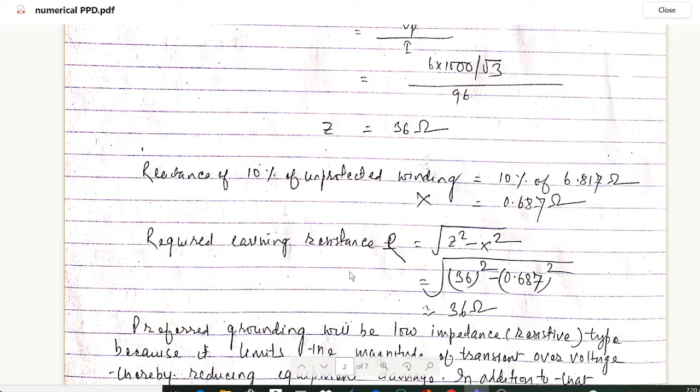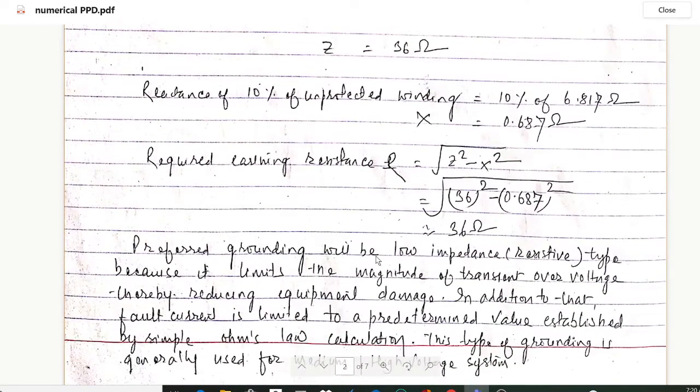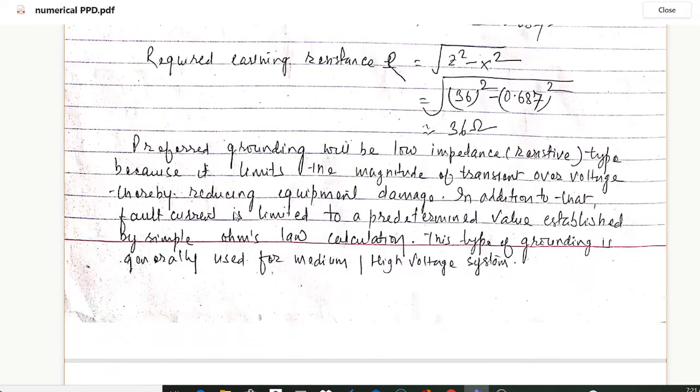Now required earthing resistance: since we need to calculate the required earthing resistance according to the question, it will be root of Z squared minus X squared. We have obtained the value of Z as 36 ohms and the value of X is 0.687 ohms, so the value of R will be 36 ohms.